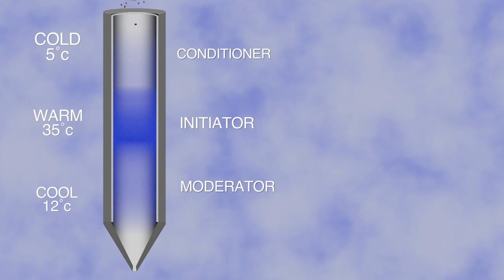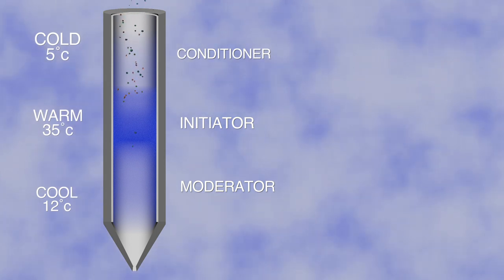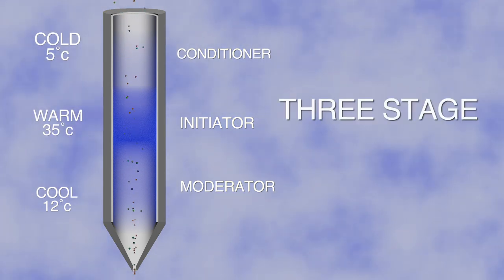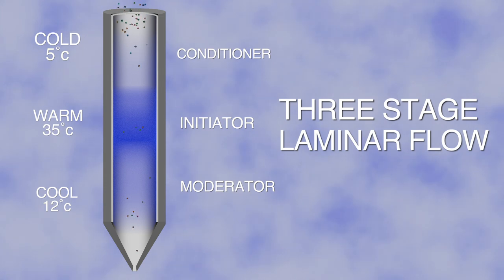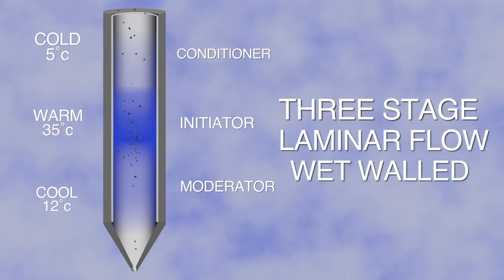Aerosol Devices core technology enlarges the size of airborne particles by condensing water vapor to form micro droplets. It uses a three-stage laminar flow tube lined with a wetted wick that creates a region of water vapor supersaturation.